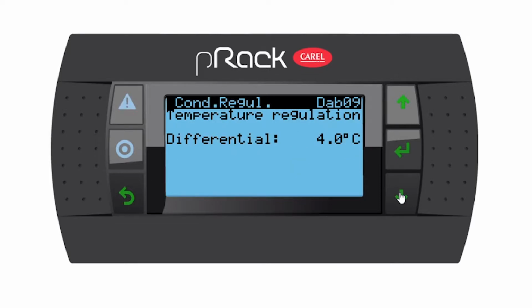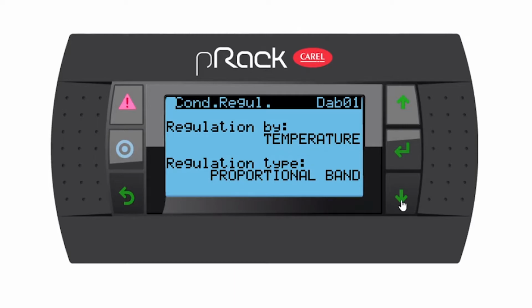Let's go down. Differential, 4 degrees. Remember, I always say put in a larger differential, maybe 4 degrees or 5 degrees, because that will just help to smoothen out the regulation on the condensing side, and also assist with fans not switching on and off too erratically. So if we go down, we're back at the beginning.